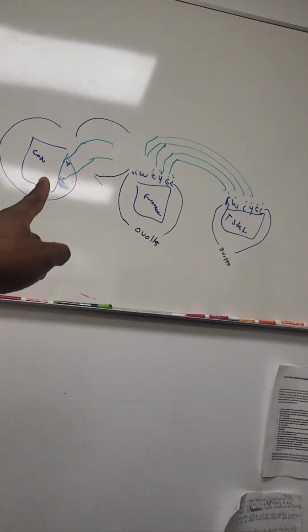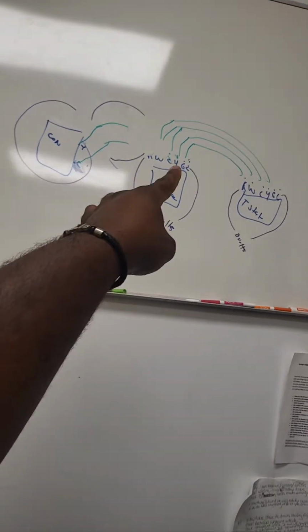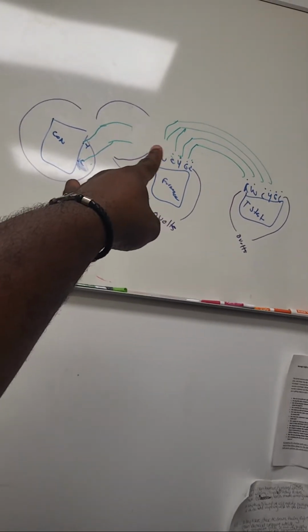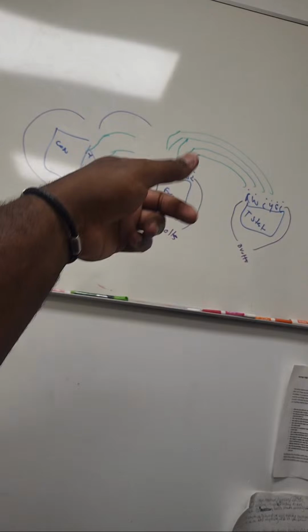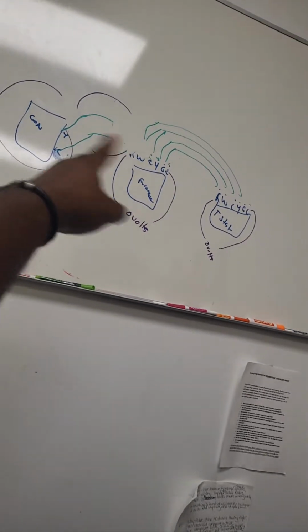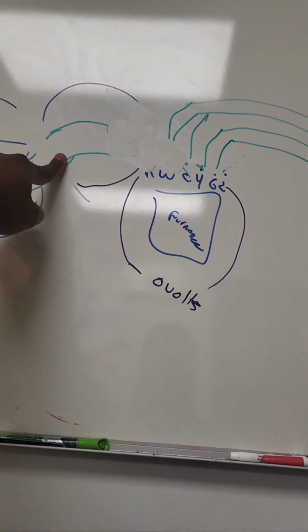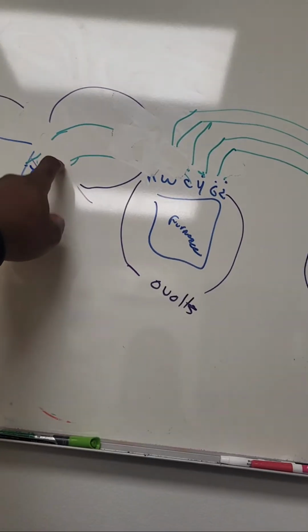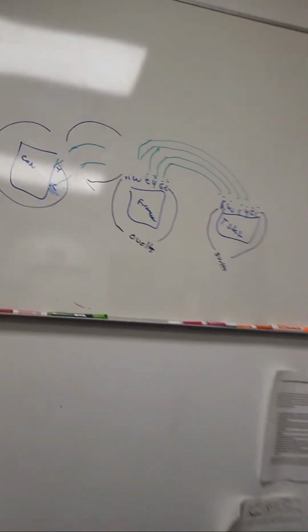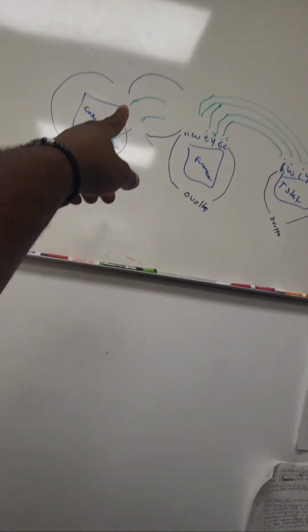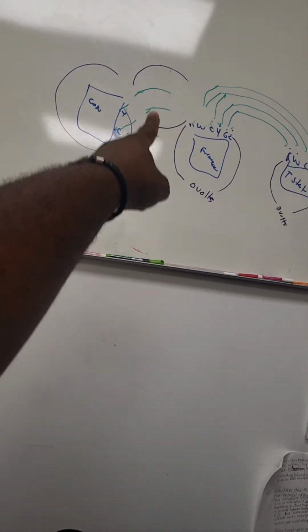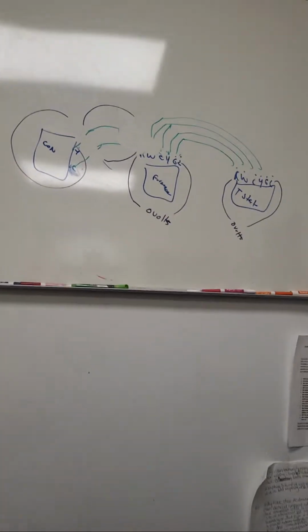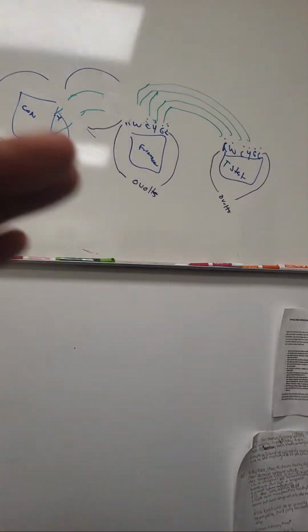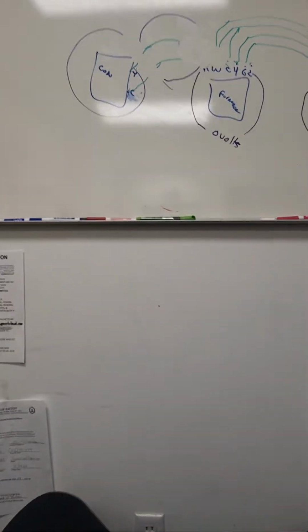Now, if something's opening on a specific side of the system - remember, I had my indoor wires hooked up and it ran. I had my outdoor wires hooked up but disconnected out here, and it worked. If my fuse would open up with my outdoor wires hooked up inside but not outside, that tells me probably one or two of my wires, maybe the C wire, are touching a piece of metal, and that's tripping my fuse.